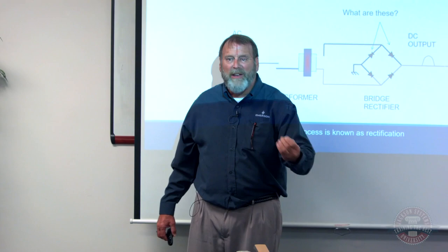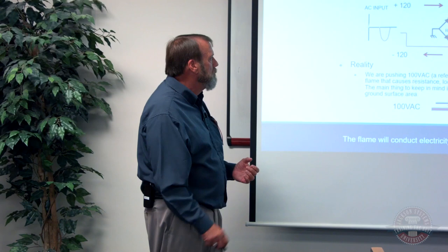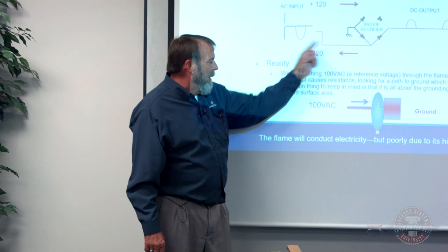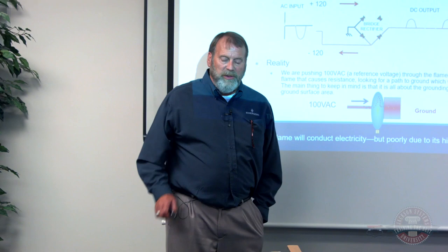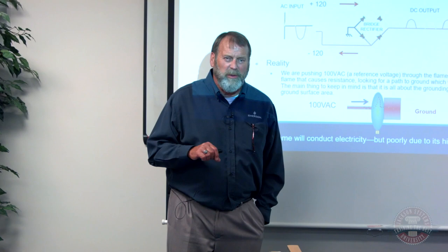And I'm going to try and explain how that works. Here's your 120 volts pulsing back and forth, back and forth, back and forth. We use 100 volts because we're looking for a reference voltage. It won't be a true 120 volts. A lot of guys ask me, is it supposed to be 120? No, it's closer to about 100 volts. Whether it be a Honeywell, a White Rodgers, Robertshaw, Fenwal, we all operate pretty much the same.